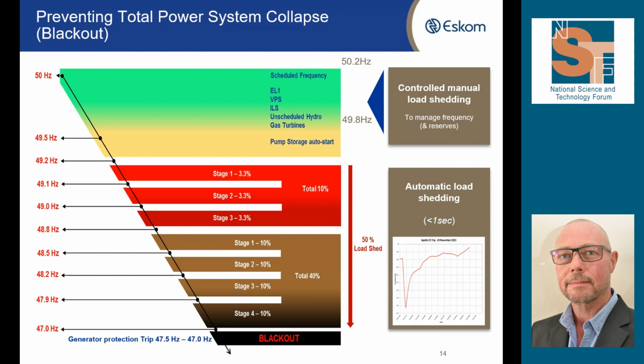What does tend to happen is, because our power system is quite vast and very high voltage, we would have tremendous disturbance in the voltages, and obviously the frequency is already disturbed. And so the power system would be in a somewhat chaotic position at that time, which we would have to then try and rectify. But if we're quick enough, we would be able to stabilize the voltage, bring it back up to 50 hertz by removing these blocks of load.